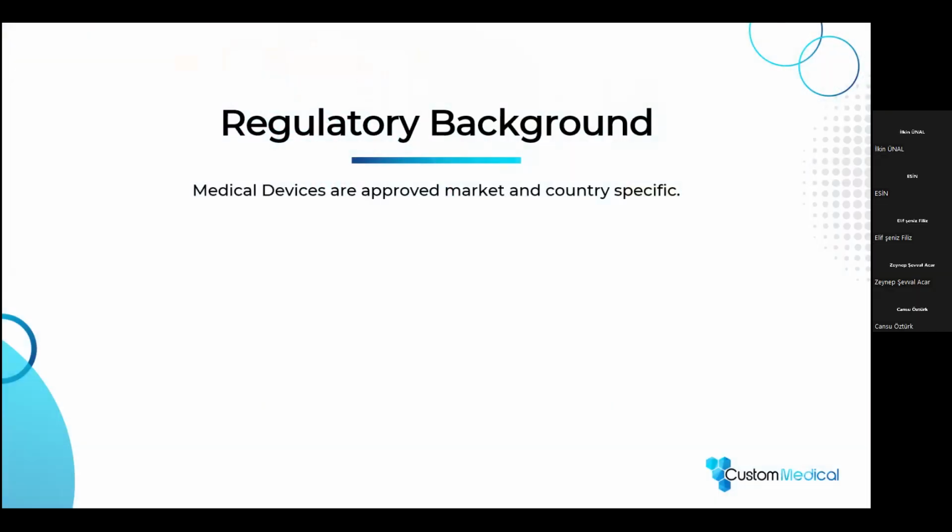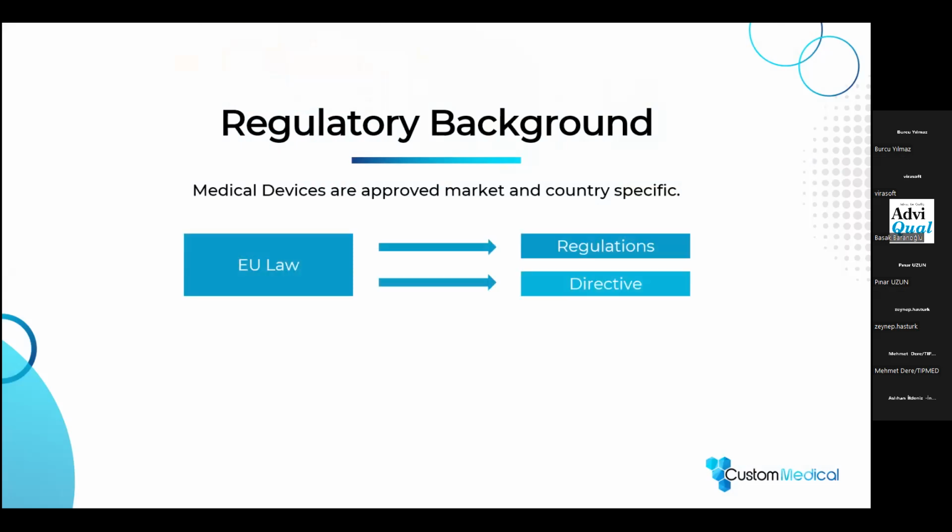Let's start directly with the regulatory background. So, as you probably all know, medical devices are approved market and country specific. But in general, for the EU, you do have the EU law with regulations and directives. The new MDR is a regulation, which therefore has to be applied by each and every country and every manufacturer who's going to the EU.